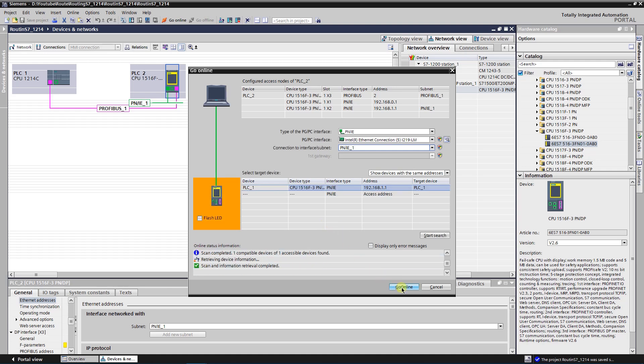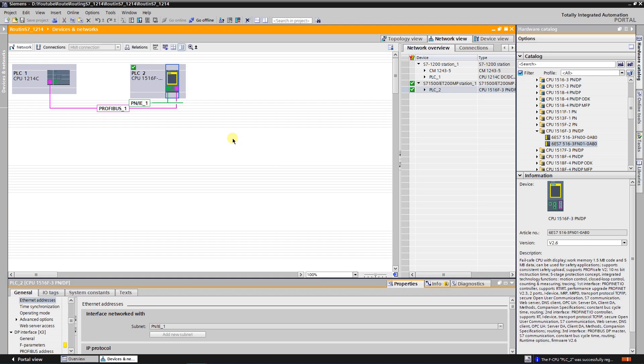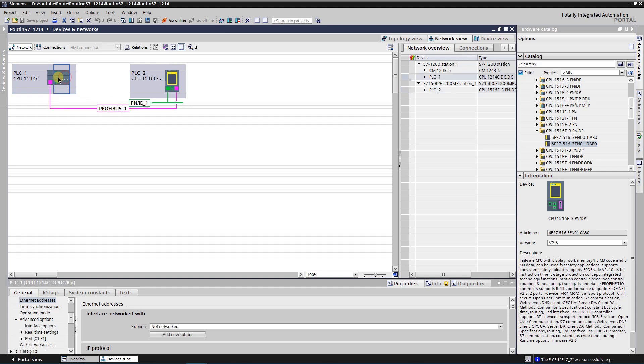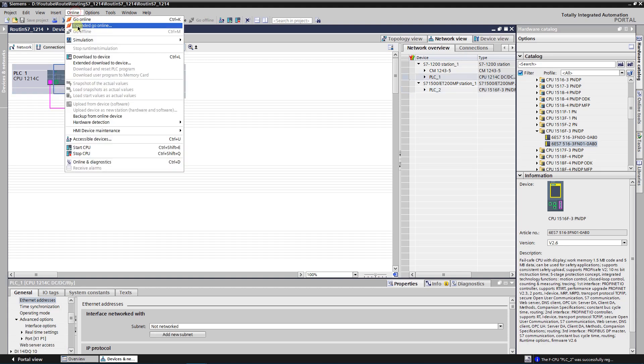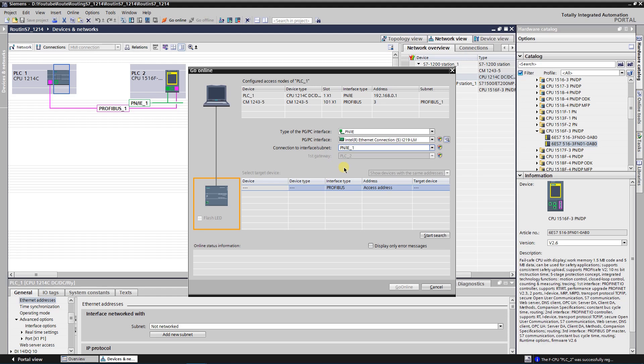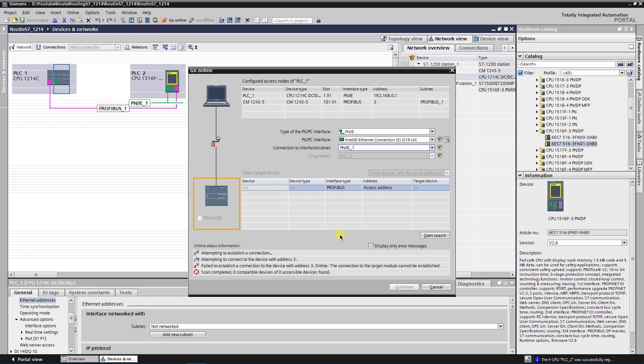So as you can see connection is established. Let's try to connect to the first CPU. Again, let's select PN/IE subnet. TIA portal added first gateway automatically. Click on search. Well, timeout has occurred as connection establishment has failed. What happened? Well, the problem is that routing configuration in the online CPU differs. It needs to be fixed.